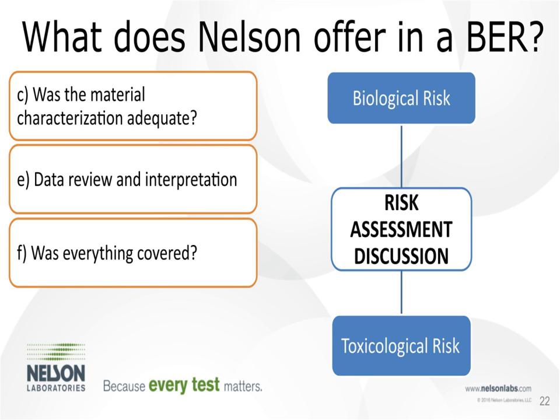We then discuss risk assessments performed. If risk assessments were used for any biological endpoints, we don't redo them — we reference and summarize their conclusions. This also addresses material characterization adequacy, which flows through several areas of the biological evaluation. We perform a data review and interpretation, linking that back to any chemistry testing done, and then assess whether the risk assessments covered everything and came to a good conclusion on device safety.